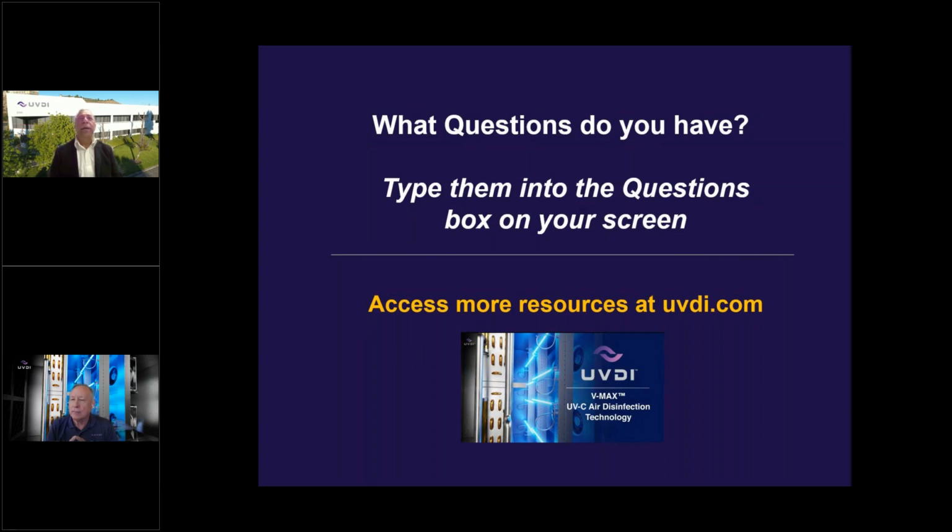It's an in-room chamber test, I think recommending a 1,000 cubic foot chamber where you can deploy any technology and measure the effect in the room, not in a duct. And there's another one which just came out last week, 185.4, which is to measure the effectiveness of UV devices for surface disinfection in a room.